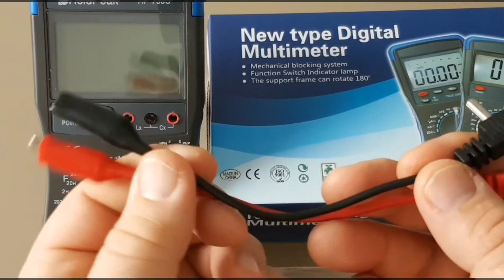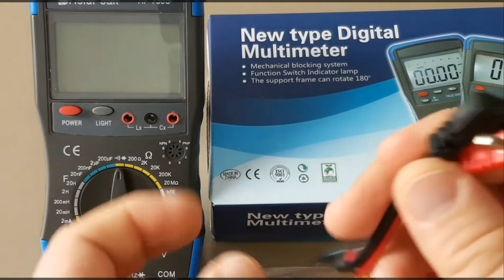Because when you're doing LCR testing, you want to have small short leads. You don't want to have a big 3-4 foot lead, because that's going to lead to impedance and mess up your measurement.